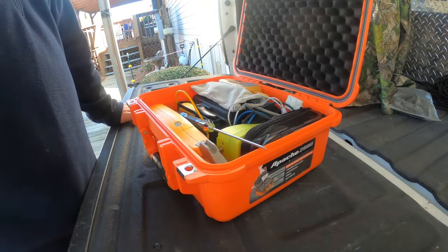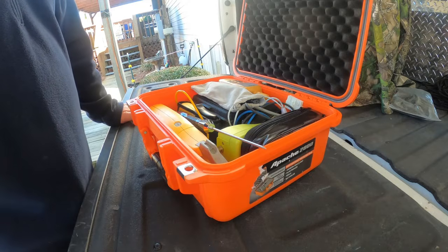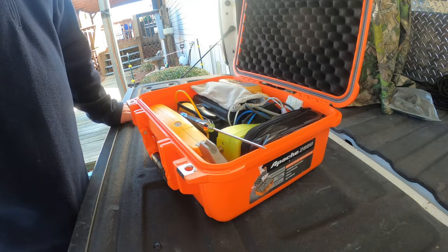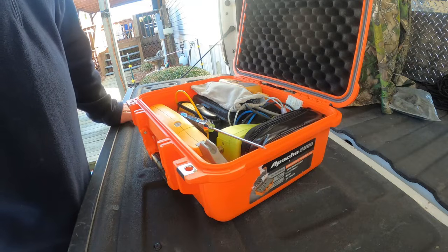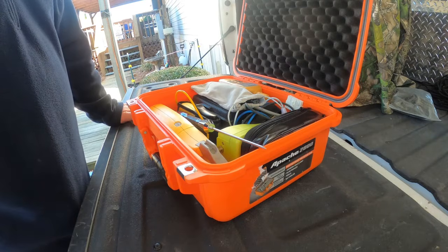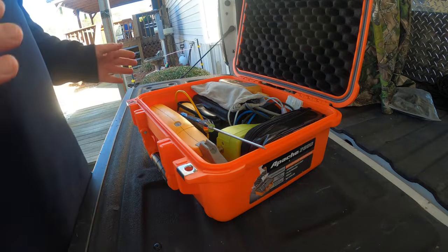You've got your permanent split capacitor motors, which basically, everybody knows those. If you open it up, there's a capacitor, it's a PSC motor. Troubleshooting those is fairly simple. Usually the motor is either locked or seized, it's shorted, you've got an open winding, or you've got a bad capacitor on it. PSC motors have different speeds.